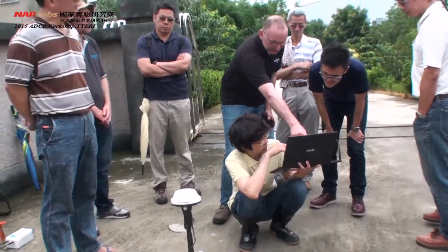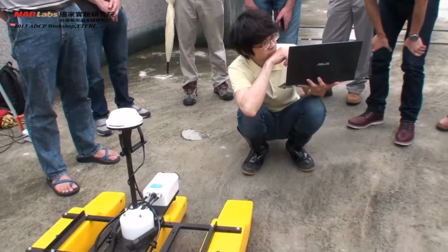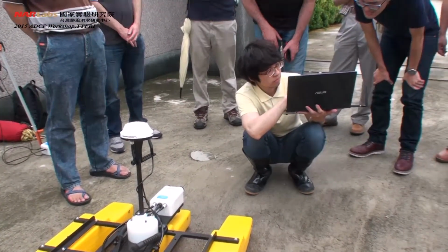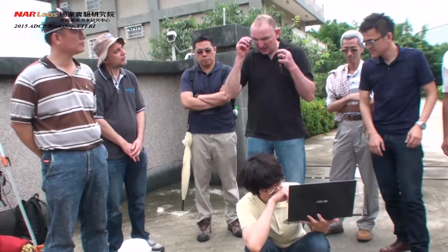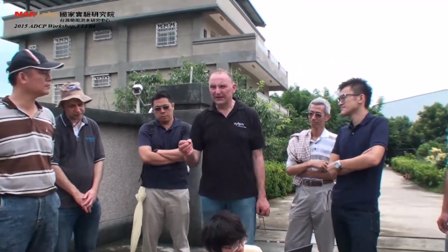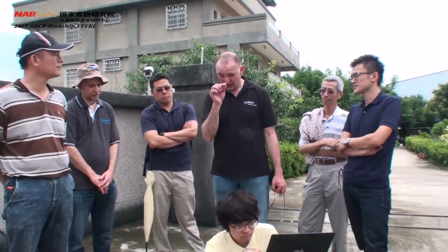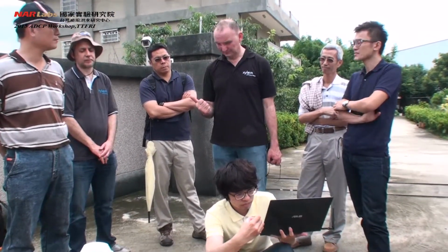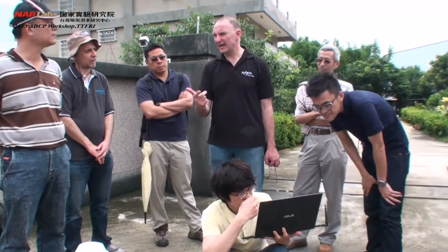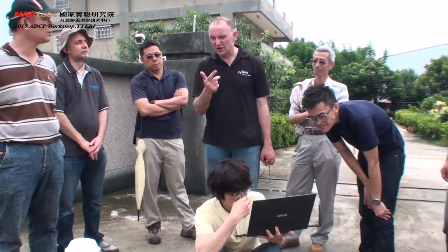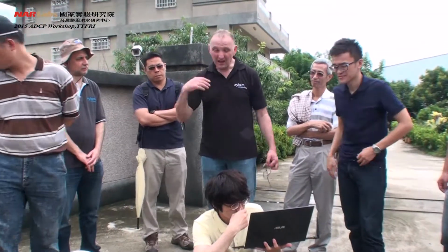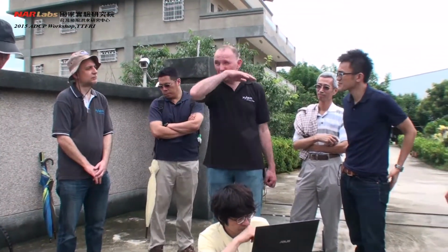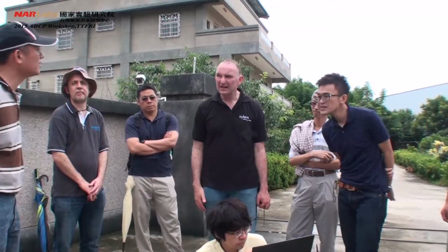There's a little sketch on there that shows you what the orientation is. Okay, so close that. The next one is track reference. We can change this in post-processing, but it's how it's going to calculate the discharge in real time. The default is bottom track. The other options are GPS using the GGA stream, the corrected stream, or the VTG stream. For standard deployment, I always just leave it as bottom track, and if I want to change it, I change it in post-processing.